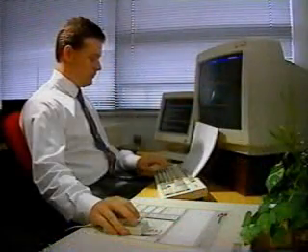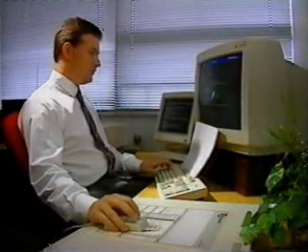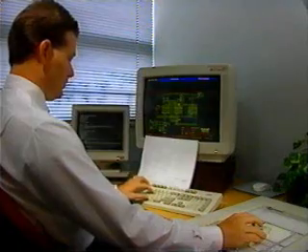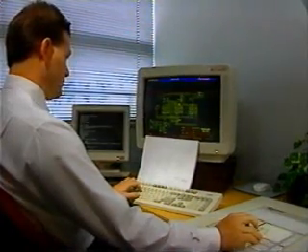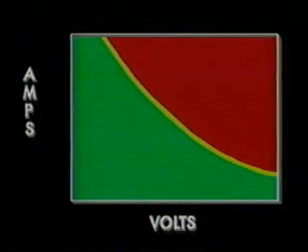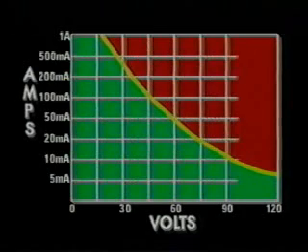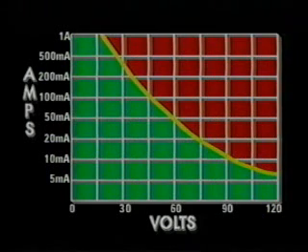That's what's happening in hazardous manufacturing areas today, as more and more designers are discovering a tool called intrinsic safety. Intrinsic safety is built on a simple premise. If a big electric current will cause an explosion in a hazardous area, and the absence of current cannot, can we identify ranges of currents that are dangerous, questionable, and safe? That's just what has been charted on ignition curves.